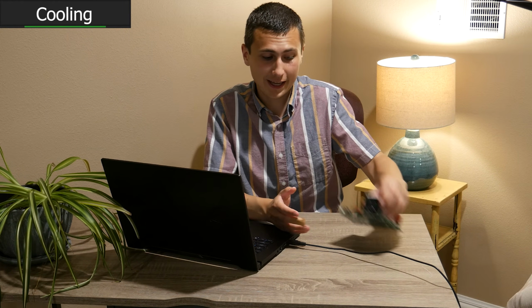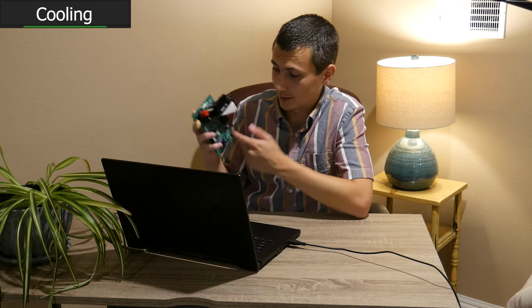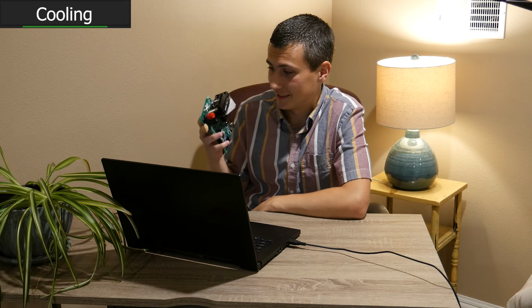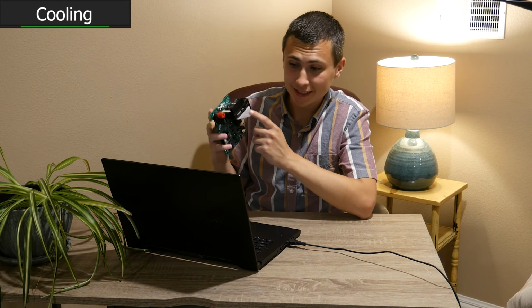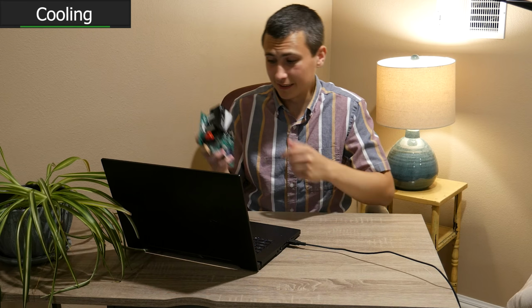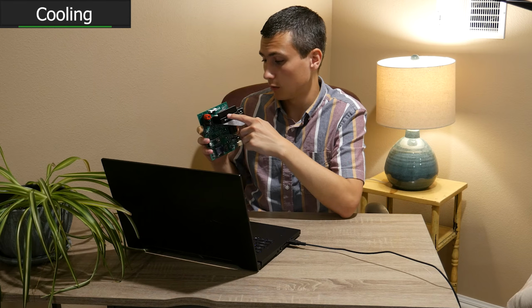It's not bad. Even though the SOA curve allows for up to 1,000 watts, practical cooling solutions simply can't handle that — we'd need sub-zero heatsink temperatures with a chiller to get that much power out of this part. But our sad little heatsink, the CR40 from Omite with the sad little 40mm fan, even with the shroud, it's just not enough. We need a better pairing, a more appropriate heatsink for this part. That's a little scary to me, because I didn't expect this to be good enough — I expected to need to improve it.